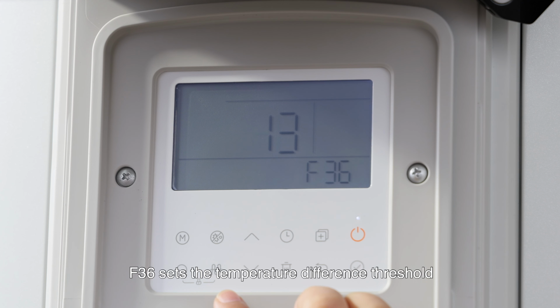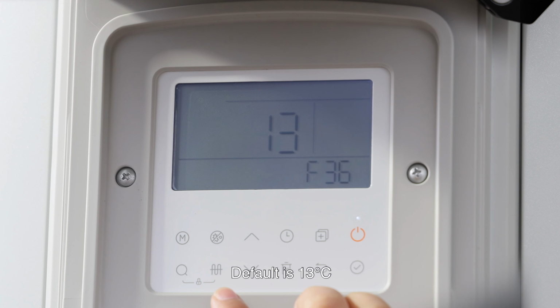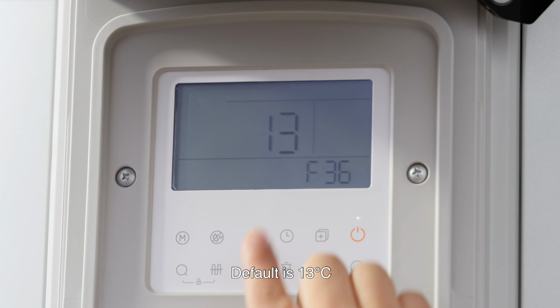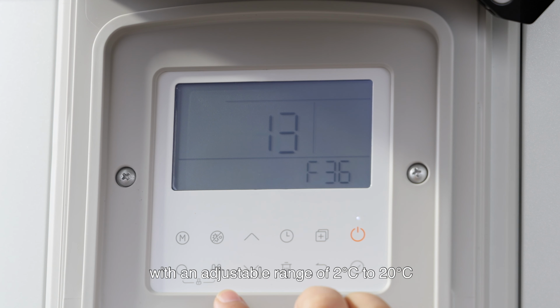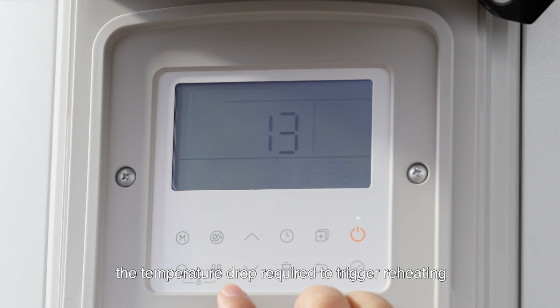F36 sets the temperature difference threshold. Default is 13 degrees Celsius, with an adjustable range of 2 degrees Celsius to 20 degrees Celsius. This parameter determines the temperature drop required to trigger reheating, resulting in shorter heating cycles when set higher. It is not recommended to set this below 5 degrees Celsius, as it may lead to system errors.